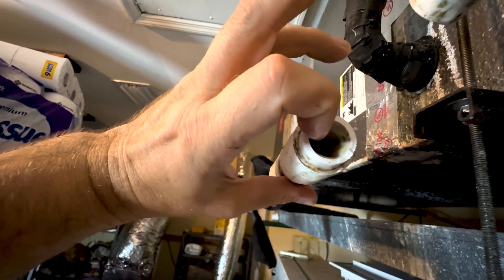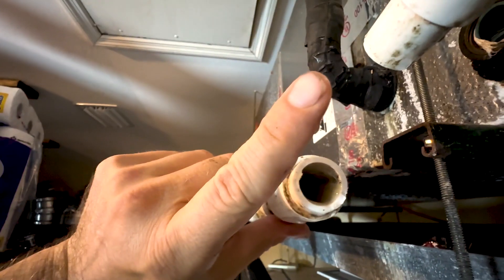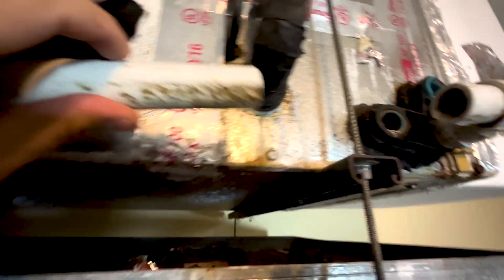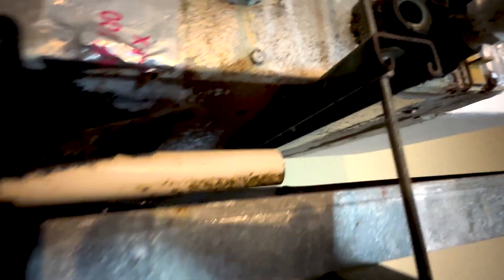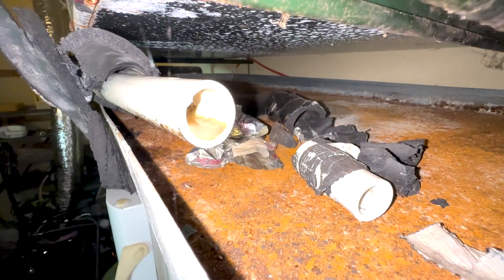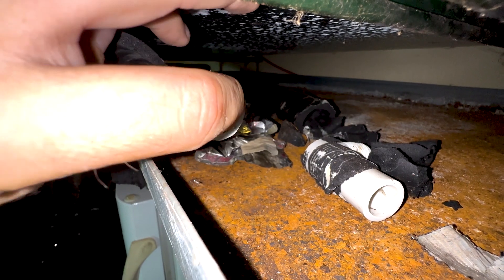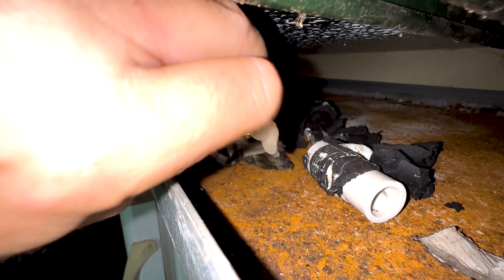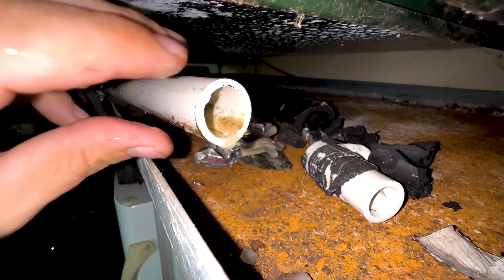Your line could be just totally filled with a bunch of junk, in which case you need to go to that video to learn how to clean it out. I'm going to go ahead and cut back right here as well. So here's one side, and there's the other side. I'm just going to leave it in there so if it drips down, it goes into the pan. So you can see, this thing has got some junk in there, right there at the bottom. That's nastiness. So it's probably time for me to clean out my drain.